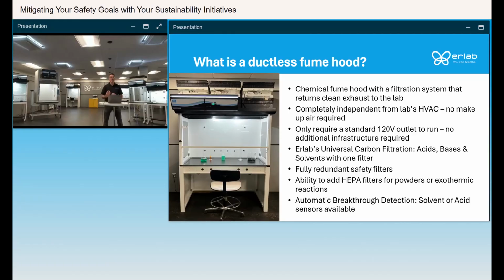That means we have a special carbon recipe through years of testing that will allow you to capture acids, bases, and solvents all with one filter. You don't need separate filters for different types of chemicals. You can use one carbon filter for that. The other thing that makes us different is our flexible filtration column. That allows for the addition of fully redundant safety filters to improve the overall safety of the hood.